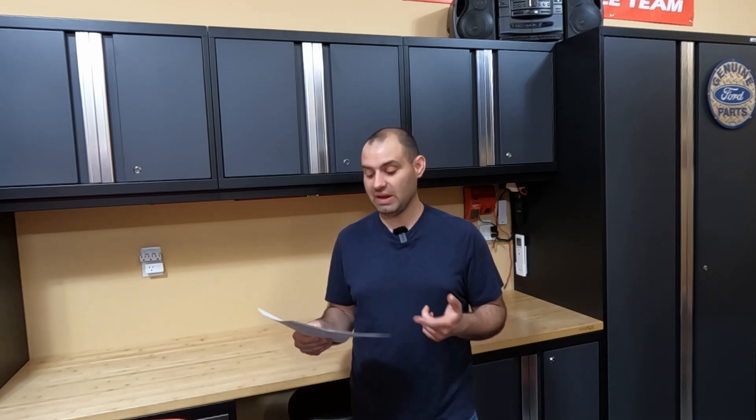If you are putting a generator into your house, make sure you do this. It's probably a good idea to do it before you put the generator in so you can get the process started. The new meter is considerably larger than the old one. Now I don't have to worry about any of my appliances becoming starved. In a situation like another Hurricane Sandy here in New Jersey — where power was out for weeks or even months — there's a good possibility everything could be running at one time. With the new 425 CFH meter able to hold double its rating, I'm getting up to about 850 CFH capacity, giving me a nice margin of error to comfortably run everything simultaneously.